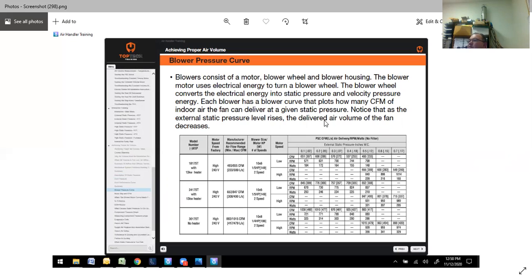So blowers consist of a blower motor, wheel, and housing. The blower motor uses electrical energy to turn the wheel. The blower wheel converts the electrical energy into static pressure and velocity pressure. Every system has a blower curve that plots how many CFM of indoor air the fan can deliver at a given static pressure.